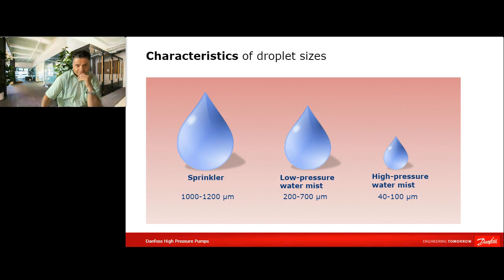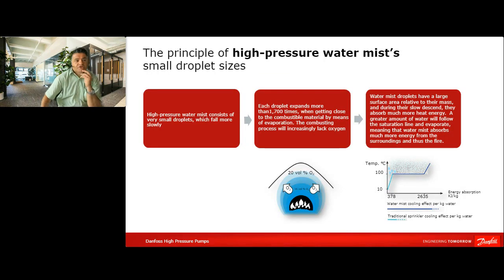Why do we do that? For two major reasons, and these are the major effects of using high pressure water mist. The one is that you put the water under pressure and make these small droplets. These droplets are distributed out of the nozzle head and come around the fire source. As soon as they have reached the fire source, they vaporize, they change their condition from liquid to gas. And by this, they enlarge their volume up to 1,500 to 1,600 times more.